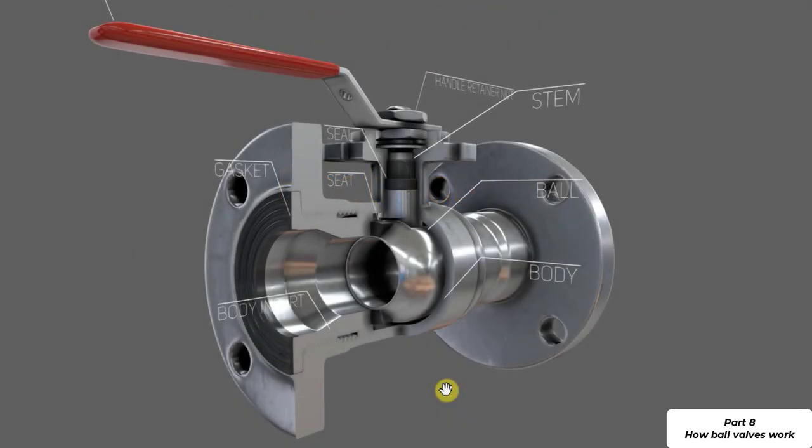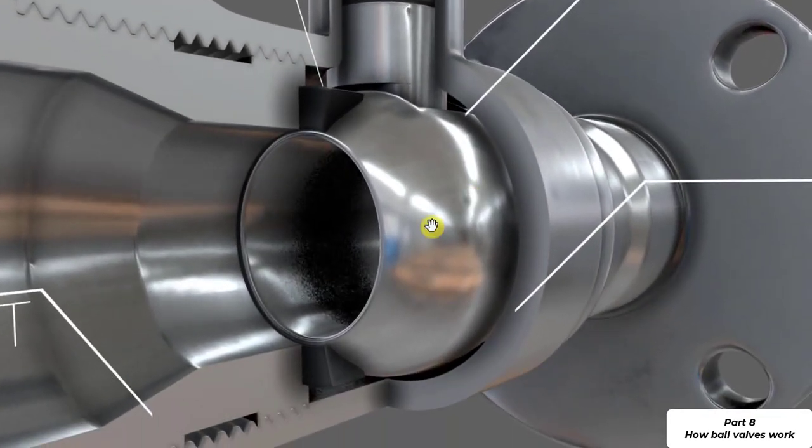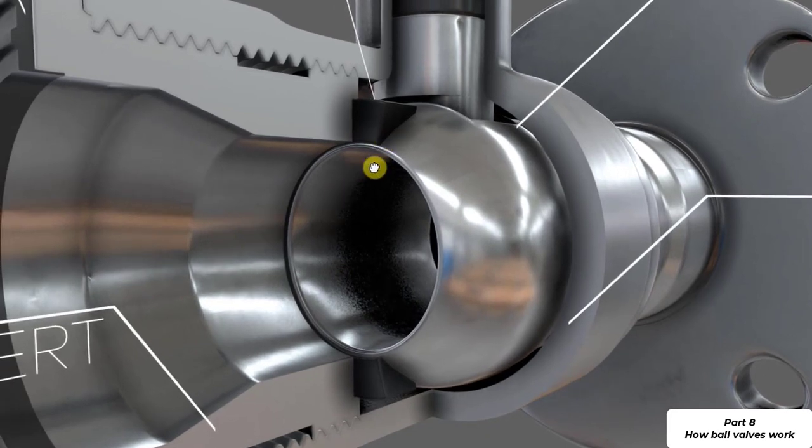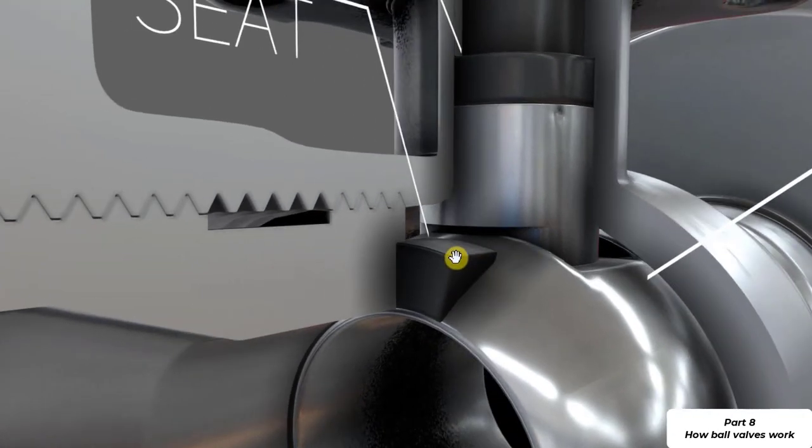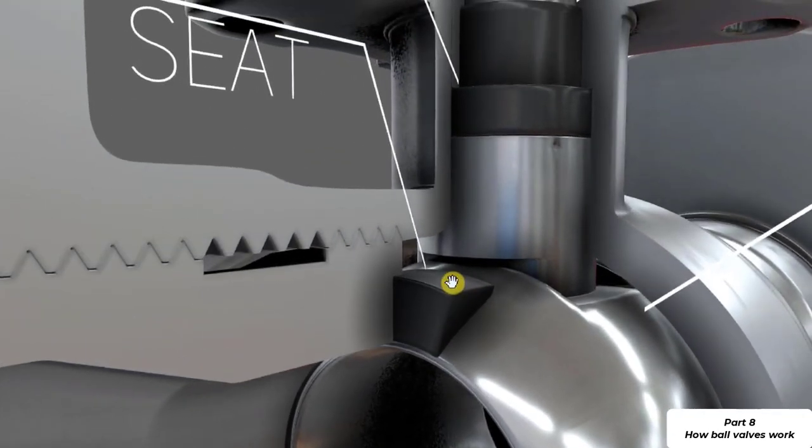As you can see the disc is manufactured of a metal material, looks to be stainless steel as is the body itself. The seat is manufactured from a softer material and this is going to be perhaps teflon or some type of elastomeric material, perhaps neoprene or a stiff rubbery type of material. This allows us to press the disc in tight against the seat and we get a really good seal.